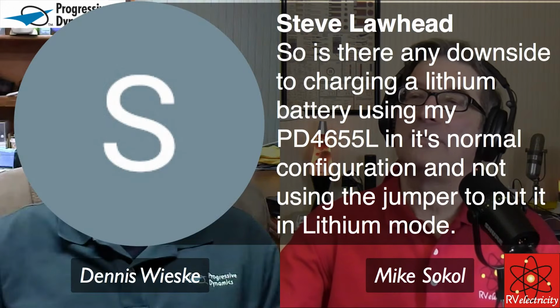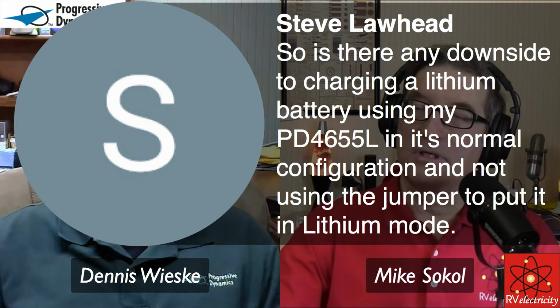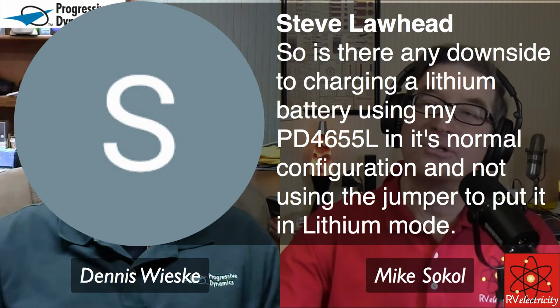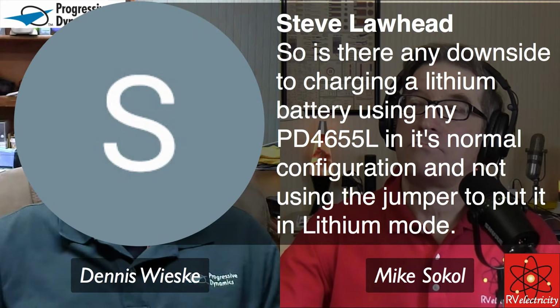Steve asks, is there any downside of charging a lithium battery using my PD4655L in its normal configuration and not using the jumper to put it into lithium mode? So Steve, we're using a standard multi-stage charger. At the normal charge rate of 13.6, you'll put a slow charge into the battery. Most battery manufacturers don't recommend it because you probably won't get a full charge - you'll get pretty close, maybe 90%, might do a little better, but it'll take forever. Charging at a slow rate may take 8 hours to do what you could do in an hour and a half at a rapid charge.